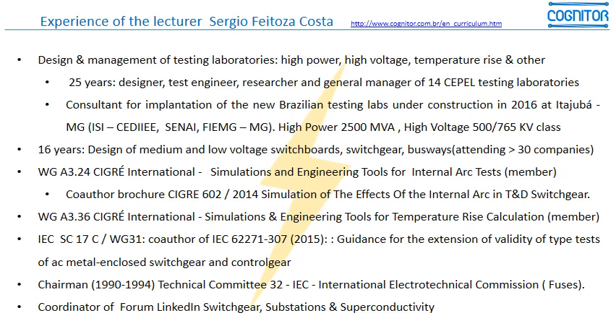I also recently worked in working group 31 of the IEC, the International Electrotechnical Commission, which prepared the new technical report IEC 62271-307, published last year. This is a guidance document for the extension of validity of type tests on medium voltage switchgear.